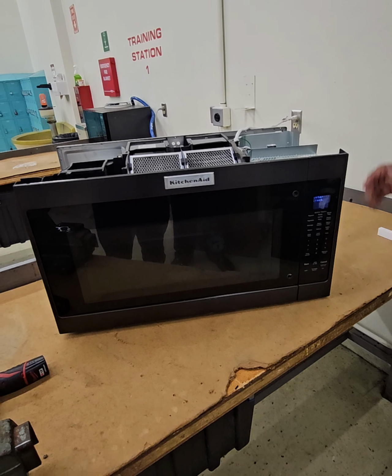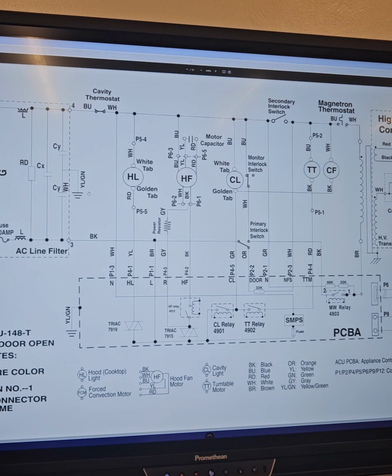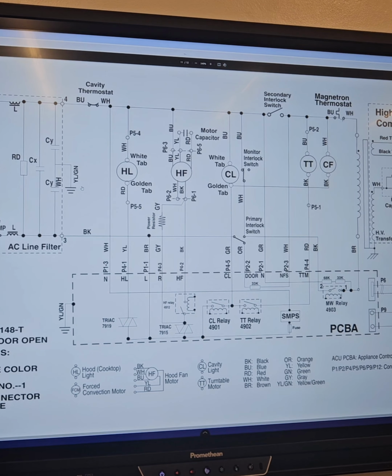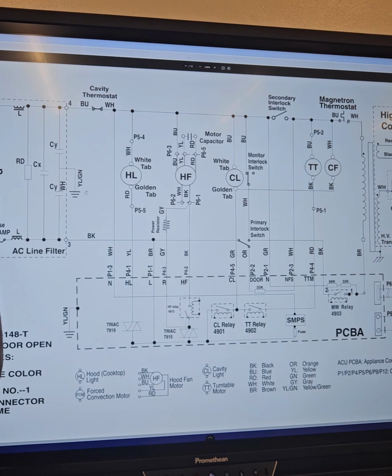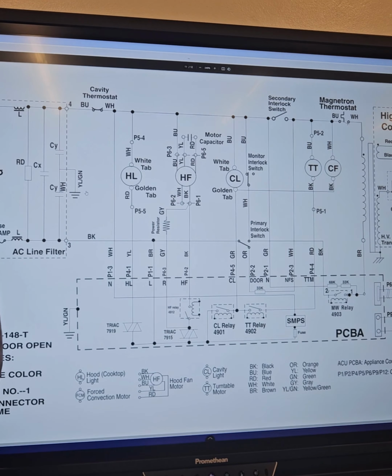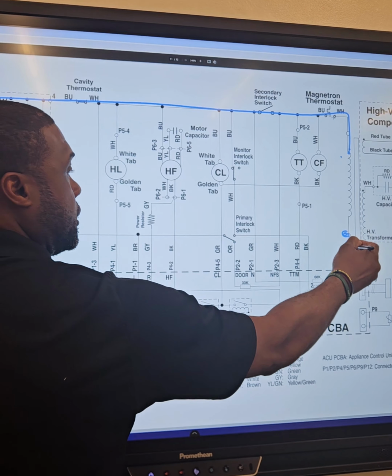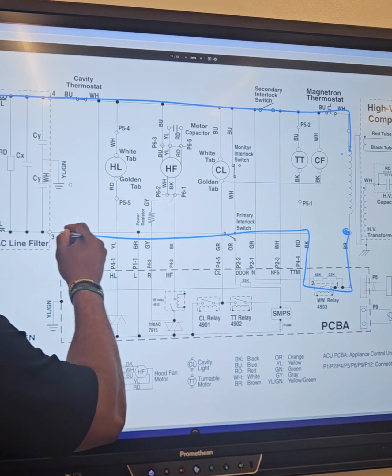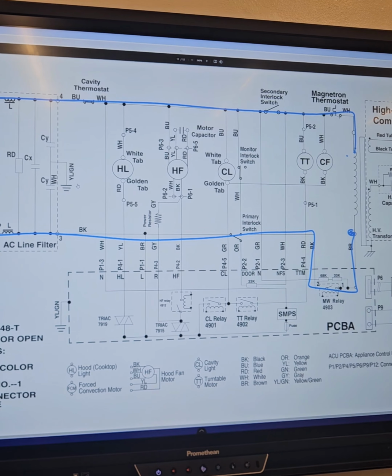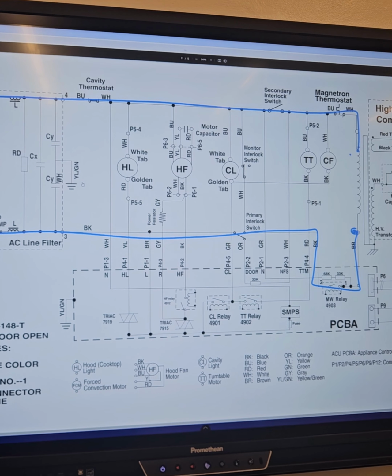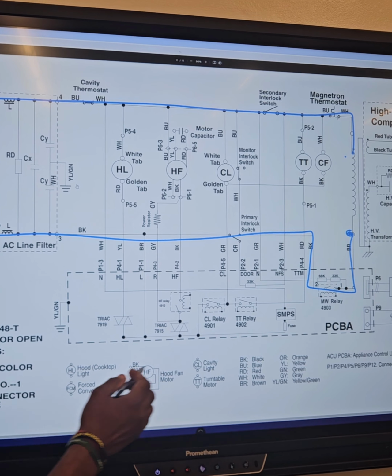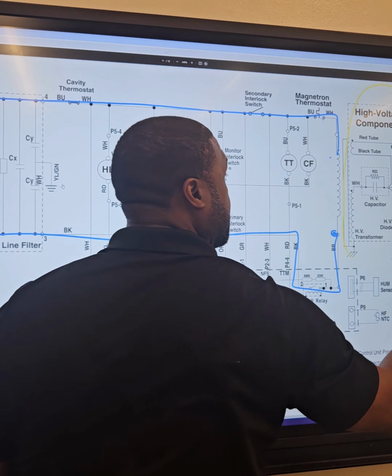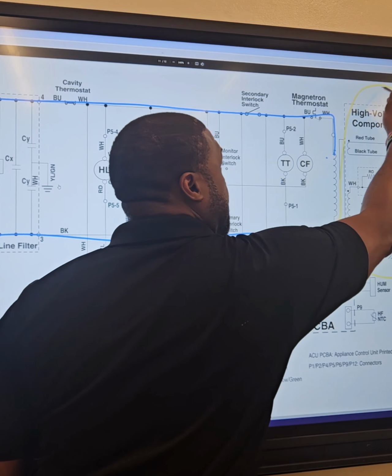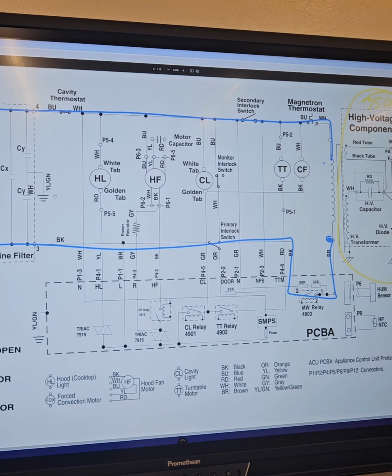All right, so we have a schematic diagram of the microwave. So let's go ahead and trace the diagram so we can see what we're gonna check. In the blue, we're gonna trace the low side, which is the 120 volt section, and we trace it to the primary winding of the transformer. We're gonna go back to the relay and back to the source. So that is your low voltage section. And in yellow, this would be our high voltage section. This section is 3,500 volts. So we're not checking any voltage on that section.